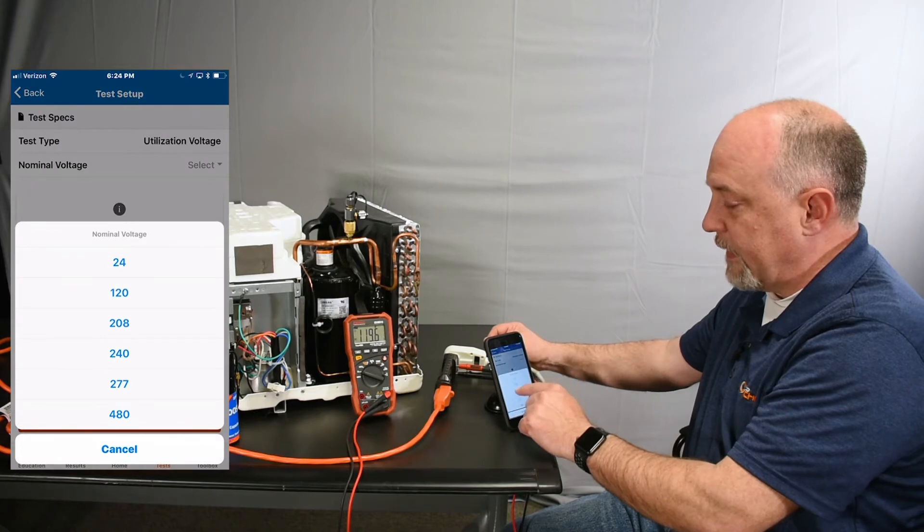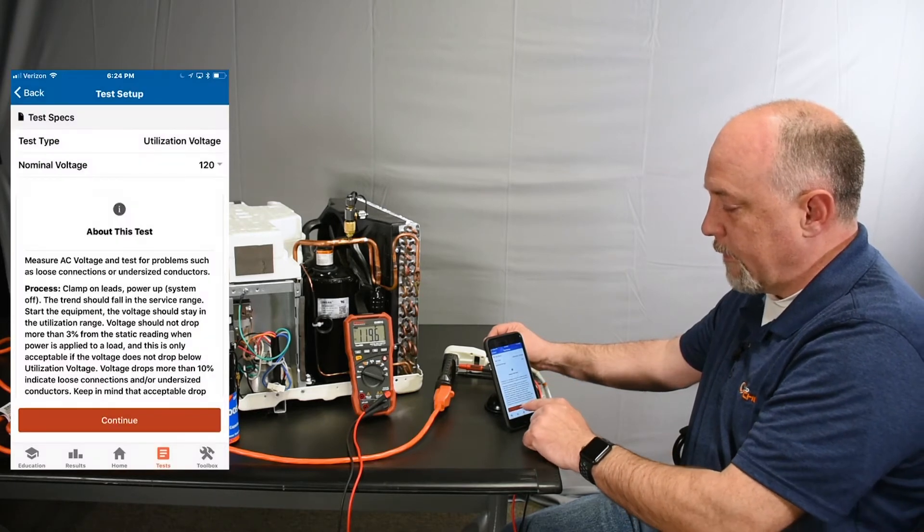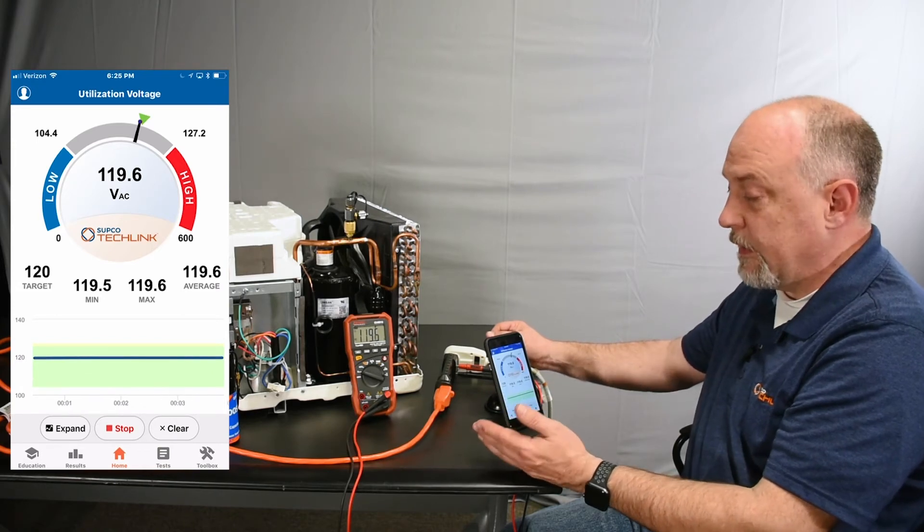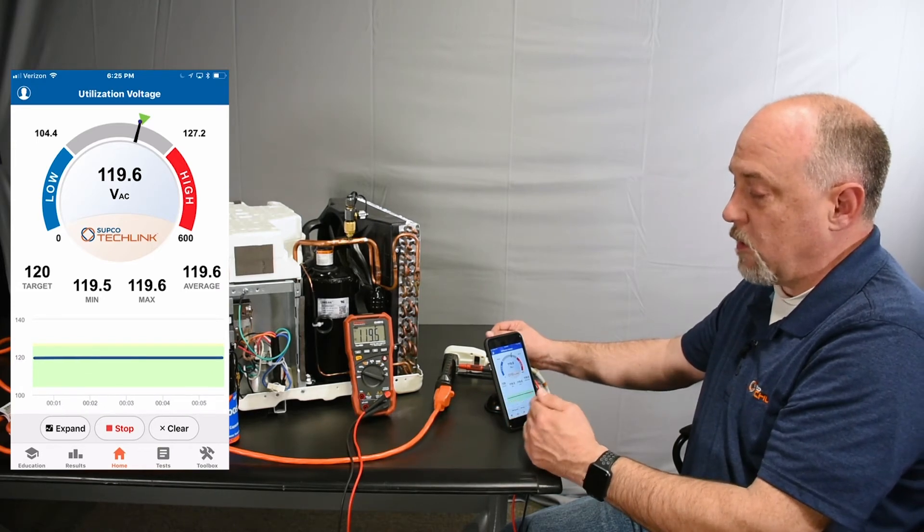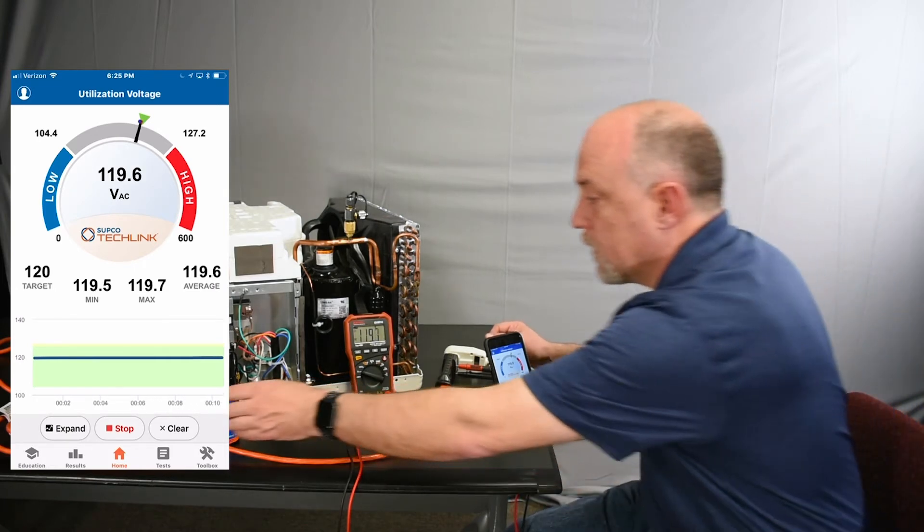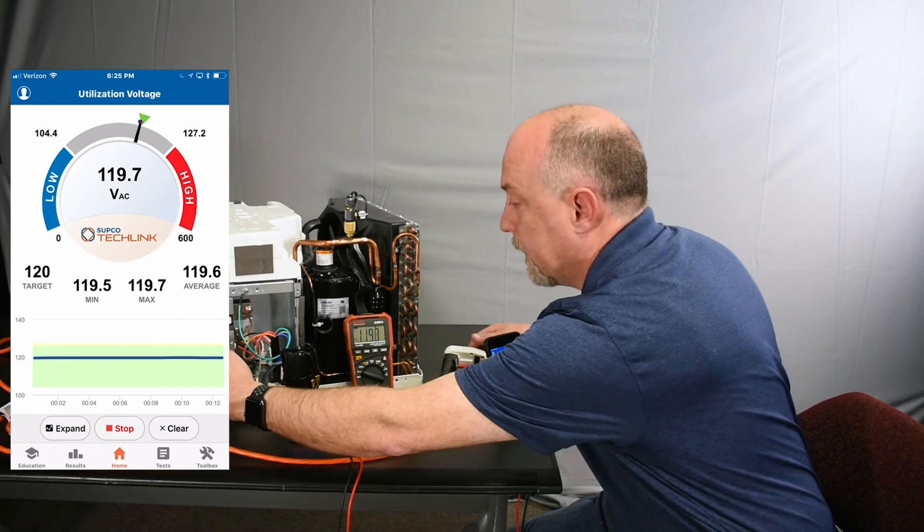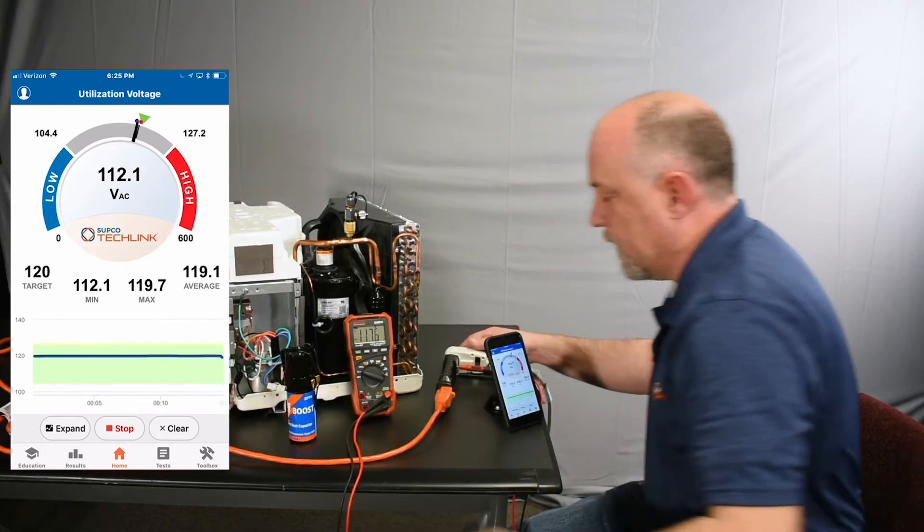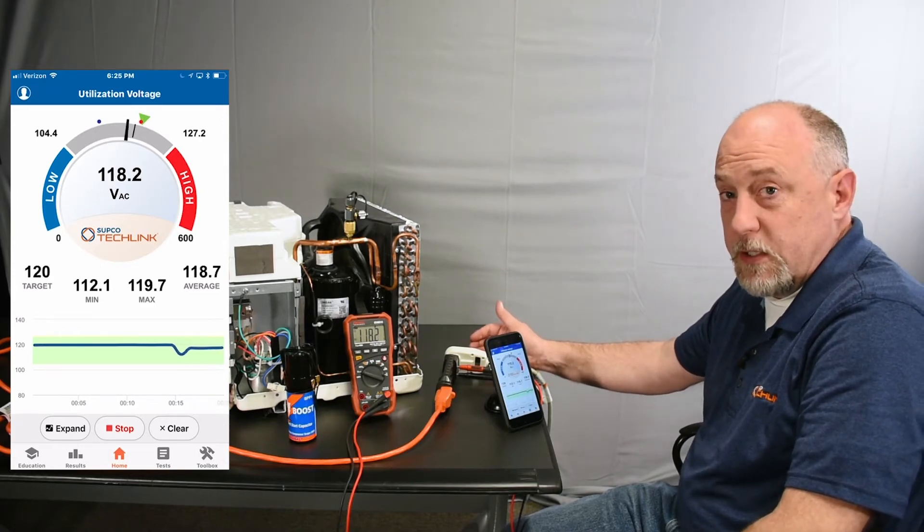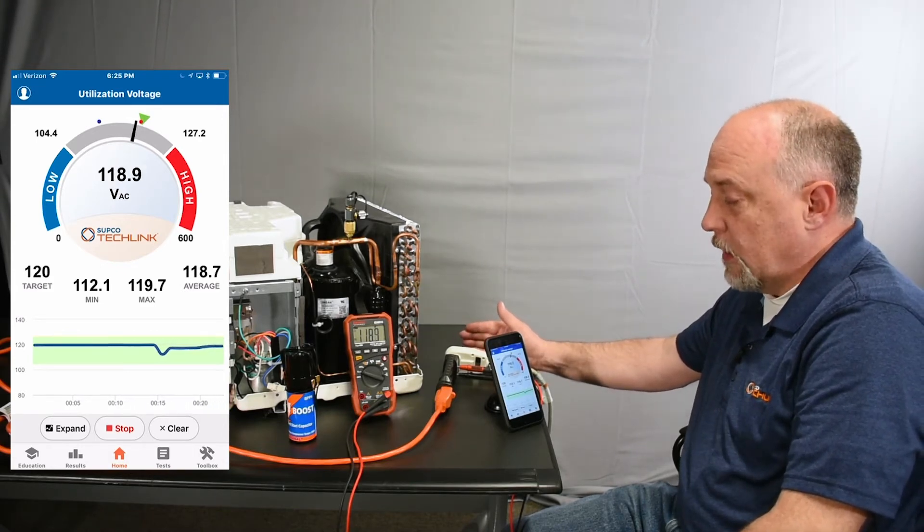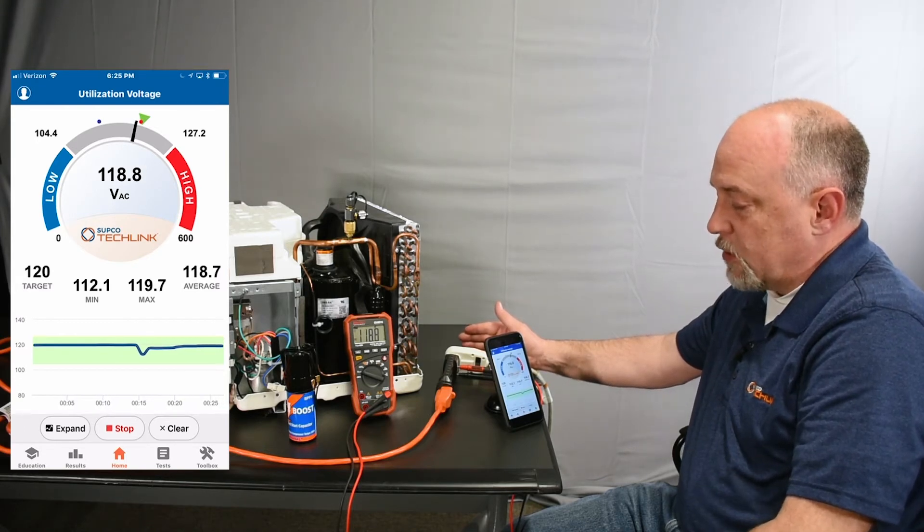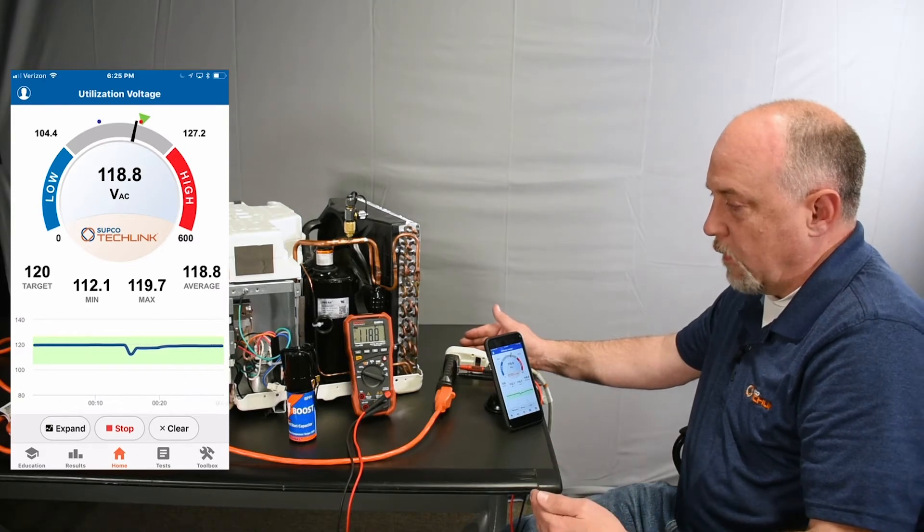Utilization is different in that the unit is going to be on. I'll hit continue and you can see we're back at 119 volts, but our scale changed. Now our utilization voltage can go down to 104 and up to 127.2. We'll start this unit up and it starts right away. Our voltage had a small drop down to 117.2, but still well within acceptable range. At startup we dropped to 112.1 but we're right back up.